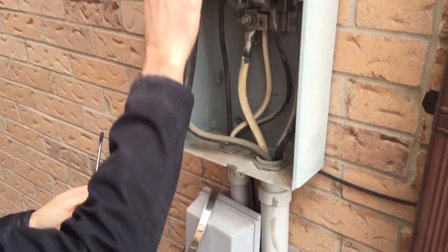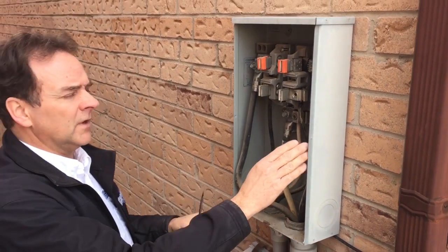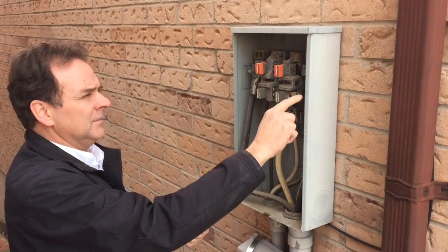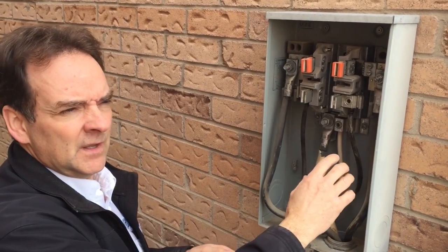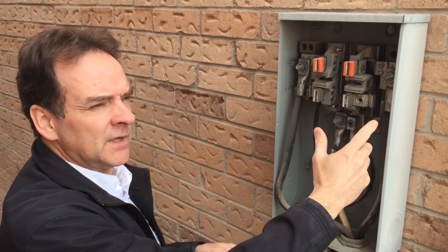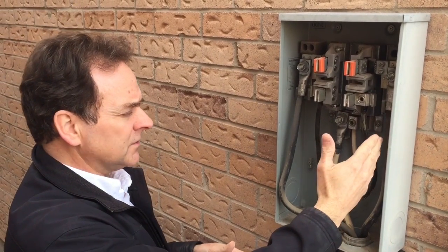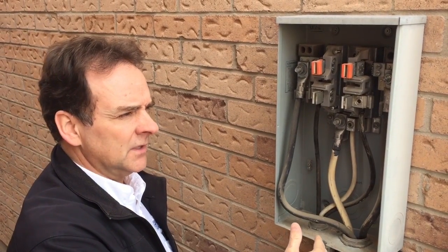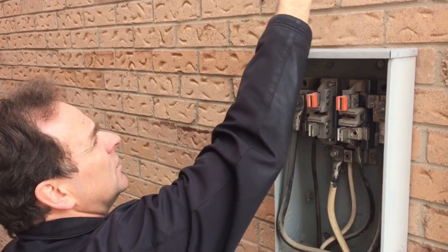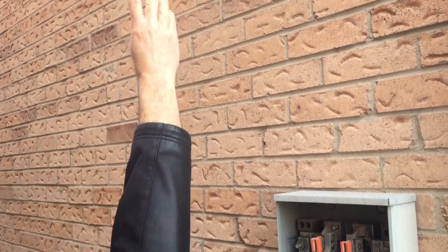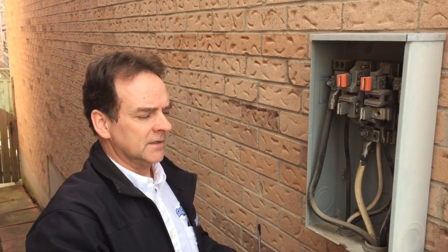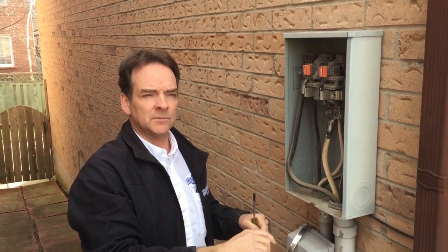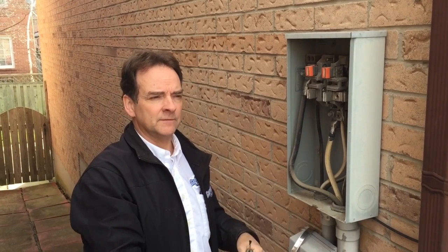So it goes obviously through the meter first. So if you have a half power problem, you could be having a situation within the meter base here where one of these components has broken down, burned up, and that would also cause half power in the house. Sometimes the conduit system goes overhead and it would go right through the roof. And those wires are connected to the utility with a crimp, and sometimes they become loose, they burn off, and that could also result in a half power scenario.